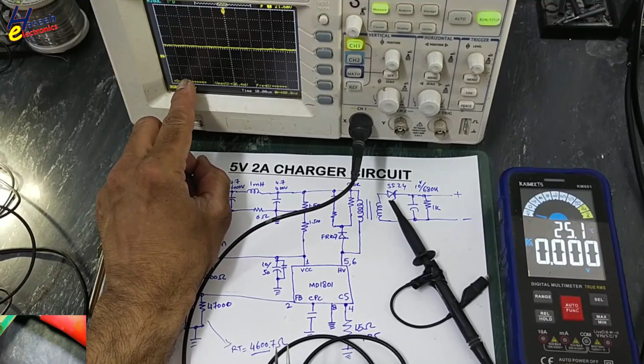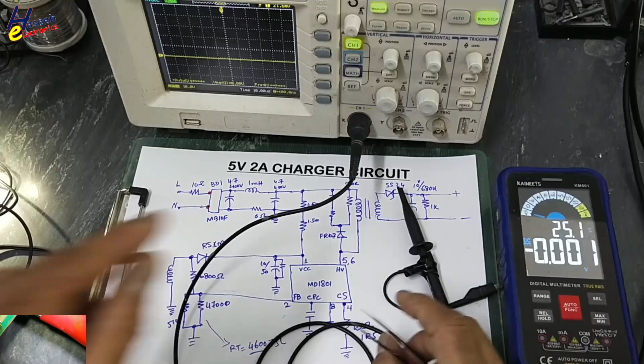We will count the number of grids in the vertical direction: 1, 2, 3, 4, 5, 6, 7, 8 grids, at a 10 volt per grid setting. 8 multiplied by 10 is 80 volts, multiplied by 10 for the probe attenuation, that is 800 volts. So this is the capability of this oscilloscope.